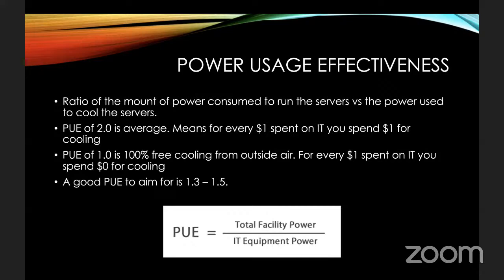Even when you're bringing that outside air in, though, the cooling may be free, but there is still an associated cost. You've got fans to drag that air in. You've got fans to circulate that air around the data center. And in places like Alaska and Norway in the winter, when it's cold, it is also very dry. So you have to humidify that air. One of the issues with very dry air inside of a data center is that you can get arcing of electricity. So conversely to not wanting a very high humidity where you're going to get condensation, you also don't want a very dry environment for the servers to be working in, because you've got possibilities there of static electricity and arcing of electricity through the dry air.